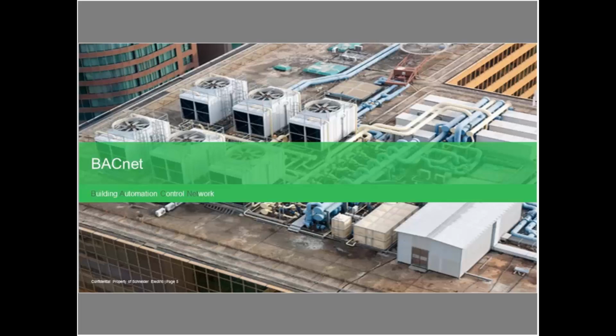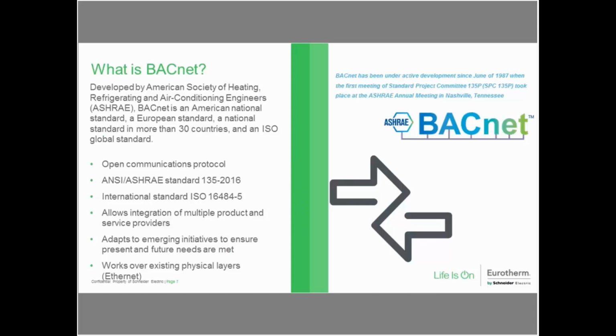So you may be familiar - BACnet is pretty much just another communications protocol that can be used to integrate other devices, instruments in a given application, control scheme, system. But just to give you a little bit of background, it is open, so much like Modbus is today. A couple other protocols out there are proprietary, we're thinking about Profinet and Ethernet IP. BACnet was built as, or more conceived as, an open protocol so that multiple vendors could be connecting to the same network under the same standards.